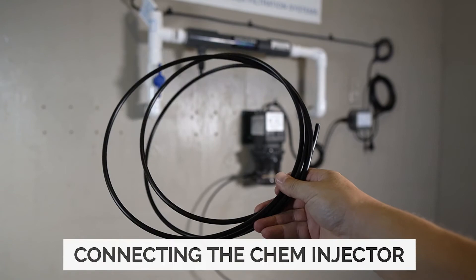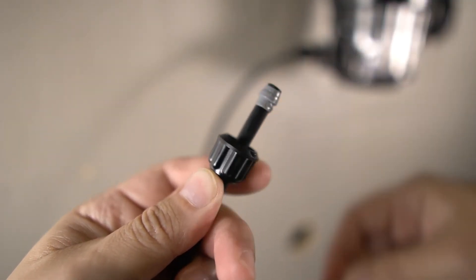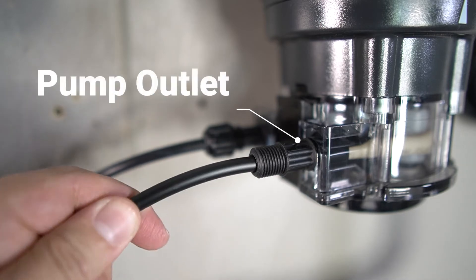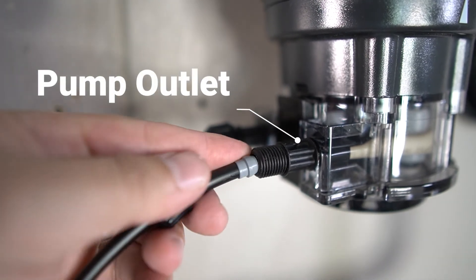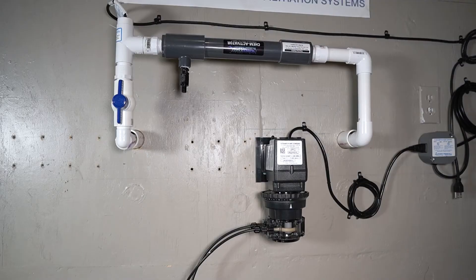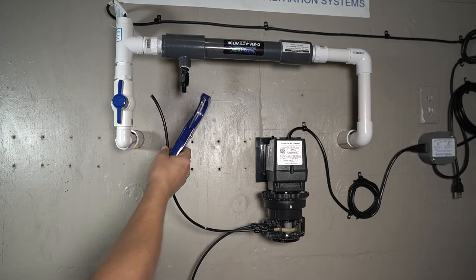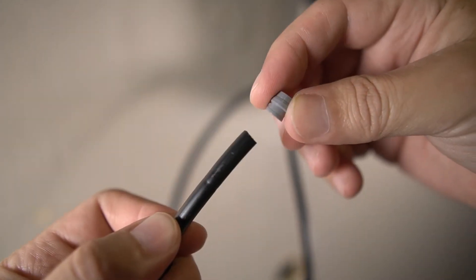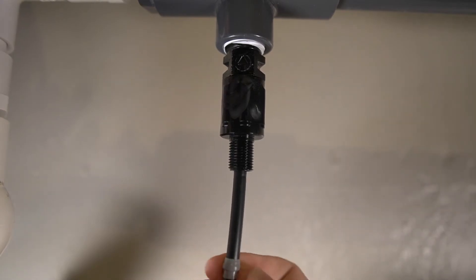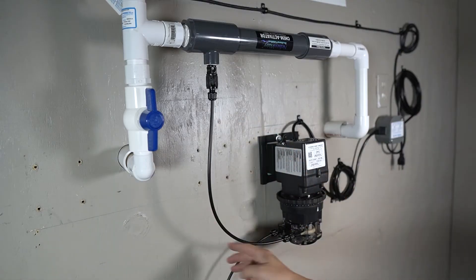The remaining tubing will be used to connect the chem injector. Slide a connecting nut over the tube with threads facing outwards, then place a ferrule on the end of the line positioned as shown. Push the tube all the way into the connection until it stops, slide the ferrule up against the connector, and fully tighten the connecting nut. Guide the other end of the tubing toward the injection fitting installed on the chem activator and trim away the extra. Again, slide a connecting nut over the tubing, followed by a ferrule, and insert the tubing into the injection fitting until it stops. Slide the ferrule into position and secure it using the connecting nut.